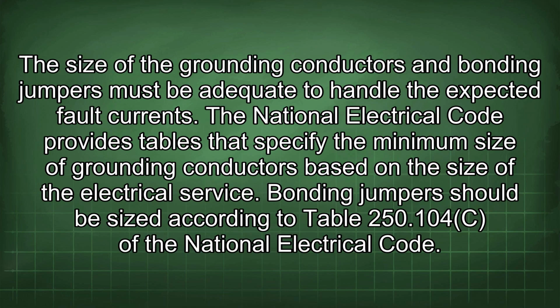The size of the grounding conductors and bonding jumpers must be adequate to handle the expected fault currents. The National Electrical Code provides tables that specify the minimum size of grounding conductors based on the size of the electrical service. Bonding jumpers should be sized according to Table 250.104C of the National Electrical Code.